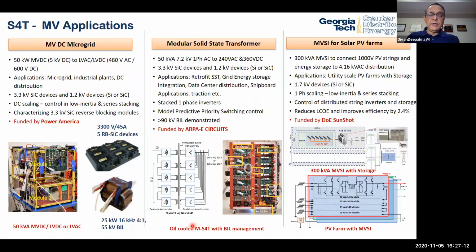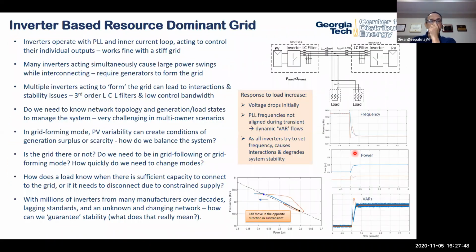So this is a very interesting topology. We've taken another example of it and built a project with SunShot, where we're doing a medium voltage string inverter at 300 kVA and 4 kV. We think that by doing distribution at medium voltage in large PV farms, we can improve efficiency by 2.4% and reduce the LCOE as well. So there are a lot of different application opportunities built around the S4T, and I don't have time to cover all of them, but this gives you a flavor for it.